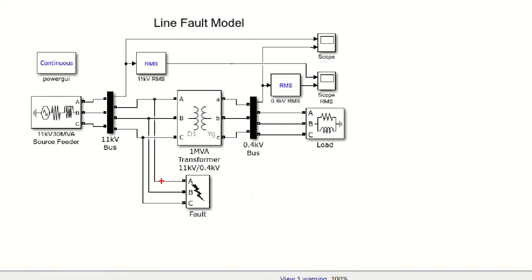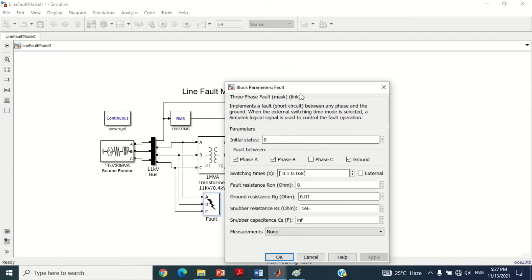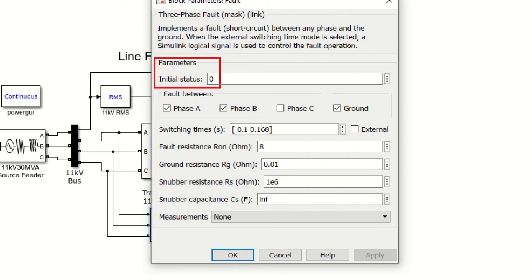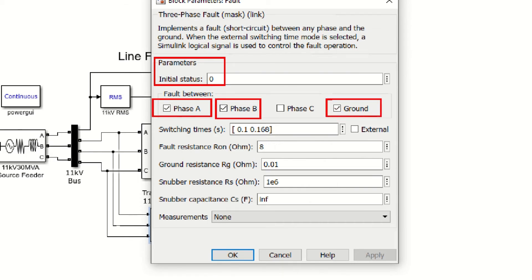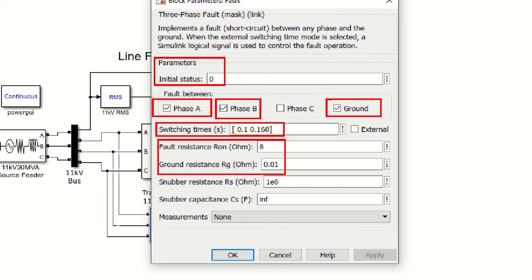Now come to another block of the model in which a 3-phase fault block is connected to apply line fault in the model. In case of line fault, the voltage magnitude is decreased. Therefore, voltage sag scenario can be simulated by applying this double line to ground fault between phase A and phase B. Double-click on this block to see its values. The initial status is set to 0, meaning that initially fault is not applied. To apply double line to ground fault, phase A, phase B and ground options are selected. Switching time is set from 0.1 seconds to 0.168 seconds, meaning the line fault will be applied at 0.1 seconds and removed at 0.168 seconds. The fault resistance and ground resistance are 8 ohm and 0.01 ohm respectively.